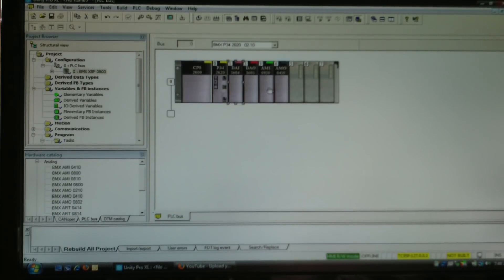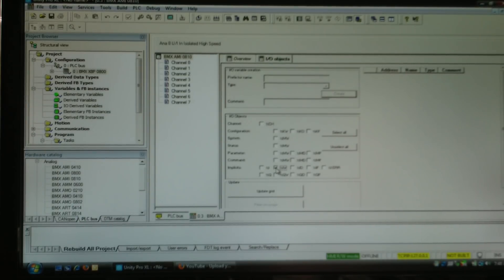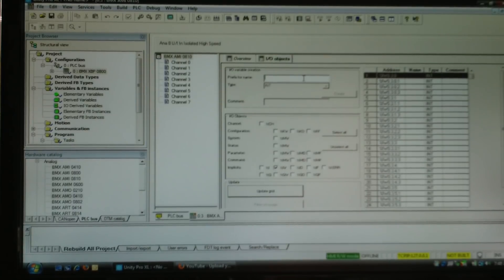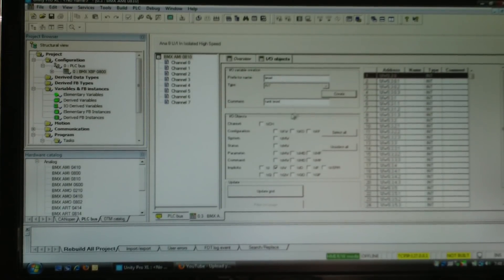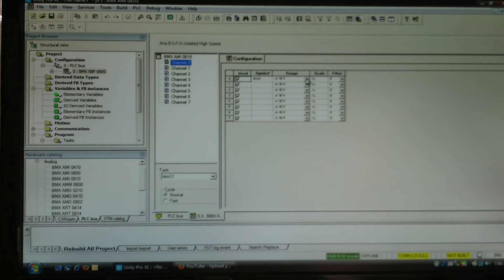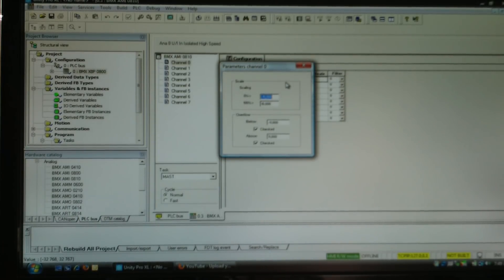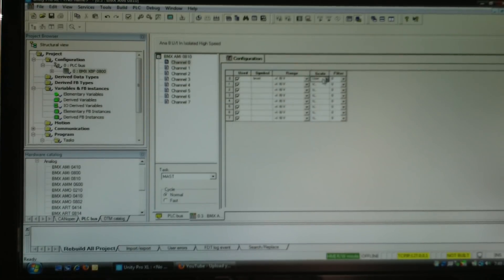If I close that and go into my analog input card — analogs have just a little bit more configuration. I'll use %iw for my analog input card and update the grid, then put a meaningful tag name in each of those and create. In the channels tab, each channel can be independently configured as ±10V, 0–10V, 0–20mA, 4–20mA, or ±20mA. You can also configure the scaling — for example, 0 might be 0 and 100% might be 500 psi — so you don't have to do that scaling in logic, which is pretty nice.